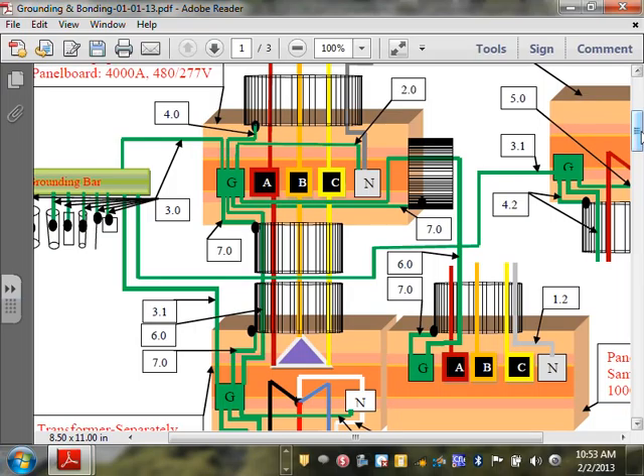In this case, suppose I have, now remember, the bottom of the switch gear is open. So I really don't have a whole lot of option when the bottom of the switch gear is open. I'm going from underground with rigid underground all the way to this sub panel here, the 1000 amp. I need to bond that rigid, the feeder. So your option of bonding, you have to have a bonding jumper, a clamp, right? Clamp on it, a bonding jumper with a bonding fitting here with a wire that goes and ties exactly like we showed, and that wire will be sized.